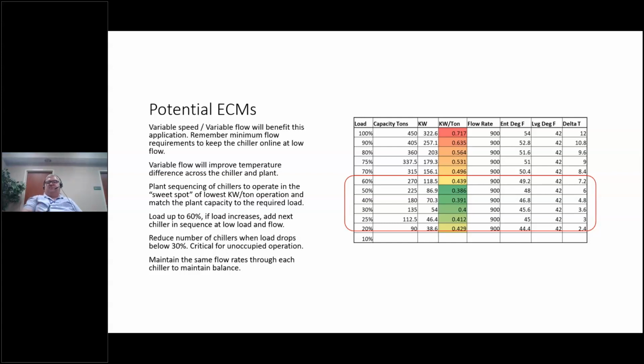Now, I notice that this chart stays at fixed flow. This is where your experience with affinity laws comes in. You start varying the flow to match your load, and again, that is going to change the profile of this machine. It will probably become more efficient because it doesn't have to work as hard when you're pumping 900 gallons a minute through it. When you can cut that in half to 450, it's not going to work as hard to accomplish your temperature difference.